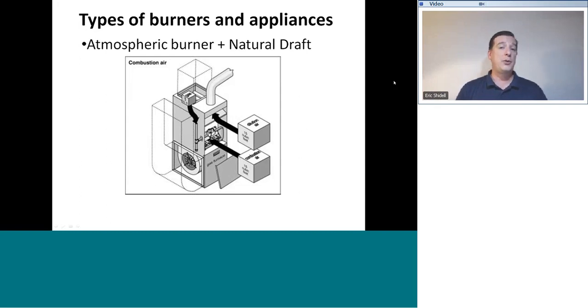An atmospheric burner with a natural draft, let's talk about the draft side first, requires additional air above and beyond the air required to support combustion. The 15 cubic feet of air required for combustion still exists. However, there is additional air that needs to be added. It's called dilution air. Let me back up. Dilution air does not help create and sustain the draft. But dilution air is drawn in because of the draft, because of that suction.